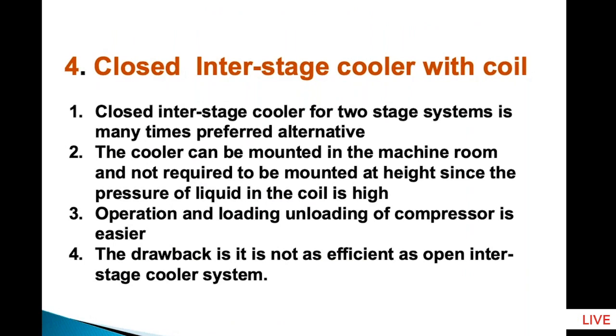I would not recommend going in for it for a new plant. With 90% of the customers using an open interstage cooler, they are not able to operate the plant. The operator creates a problem, and a compressor breakdown takes place. So the safer side is to use a closed interstage cooler with a coil, because inside the coil there is high pressure liquid, and therefore there is no problem.